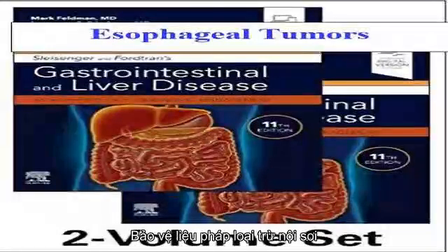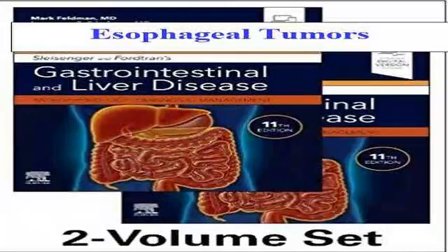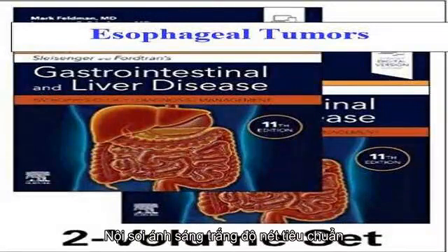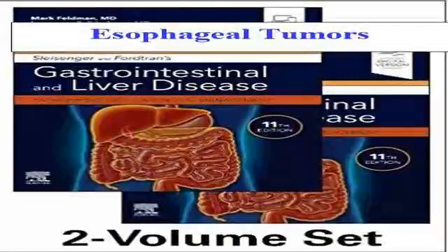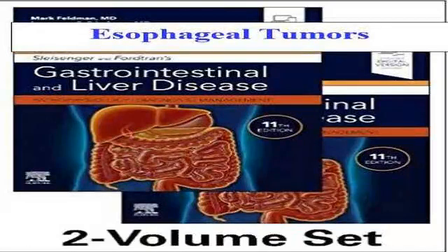Technologic advancements have allowed the creation of smaller charge-coupled device chips that are capable of producing images with high resolution, over 850,000 to 2.1 million pixels, displayed on monitors with a 16:9 aspect ratio, resulting in superior imaging quality compared to standard definition white light endoscopy, WLE. High-resolution magnification endoscopes can optically magnify images up to 150 times, although not routinely available in the USA. High-resolution endoscopy, with or without magnification endoscopes, has been shown in several studies to increase the yield for detection of dysplasia and early cancer.